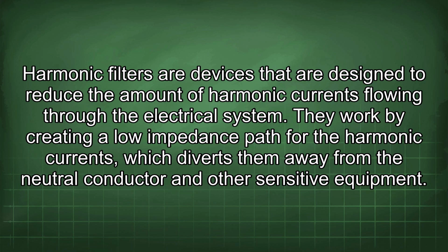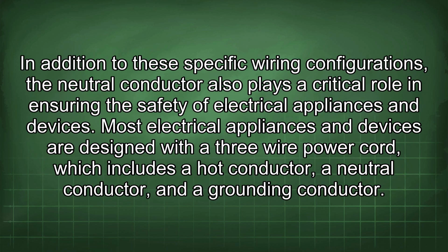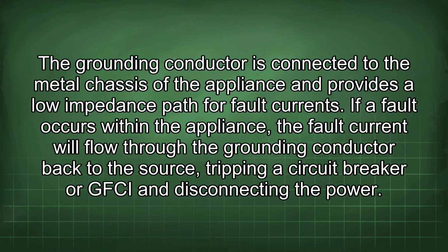Harmonic filters are devices that are designed to reduce the amount of harmonic currents flowing through the electrical system. They work by creating a low impedance path for the harmonic currents, which diverts them away from the neutral conductor and other sensitive equipment. In addition to these specific wiring configurations, the neutral conductor also plays a critical role in ensuring the safety of electrical appliances and devices. Most electrical appliances and devices are designed with a 3-wire power cord, which includes a hot conductor, a neutral conductor, and a grounding conductor. The grounding conductor is connected to the metal chassis of the appliance and provides a low impedance path for fault currents.